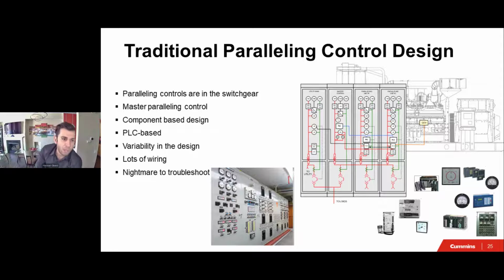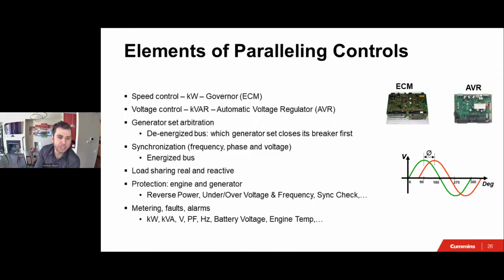However, the elements for paralleling control are, we need to have something to control the speed, kW. This is done by the governor. We also need to control the voltage, so the VAR control. And we need to do what's called the arbitration that I just talked about, basically deciding which generator set closes to the bus first. And we need to have some kind of protection and metering.